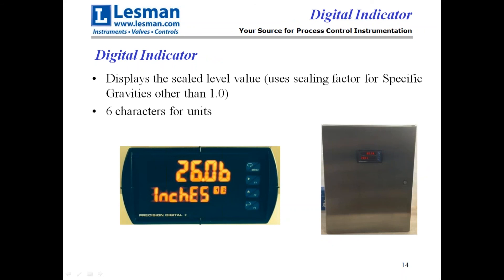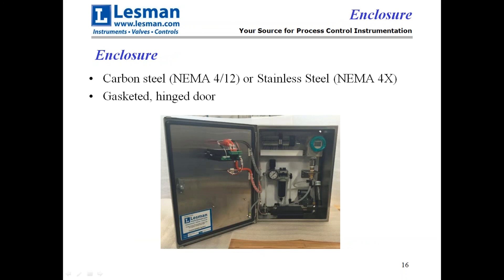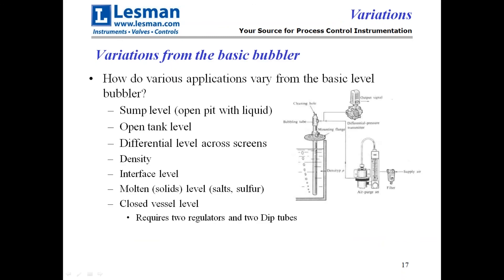The digital indicator has both digital numbers and a scale in inches, feet, or millimeters — whatever you need. There are six characters for units so you can be very clear about what you're measuring. The panel heater at the bottom keeps it from freezing in wintertime; it's thermostatically controlled so it doesn't waste energy in summer. The enclosures are either carbon steel or stainless steel, with a gasketed hinged door giving you NEMA 4 or NEMA 4X. This comes to you with all components mounted, wired, and ready to go.